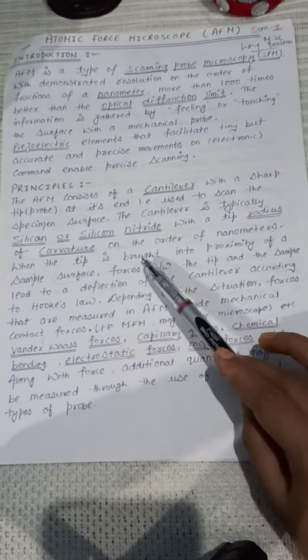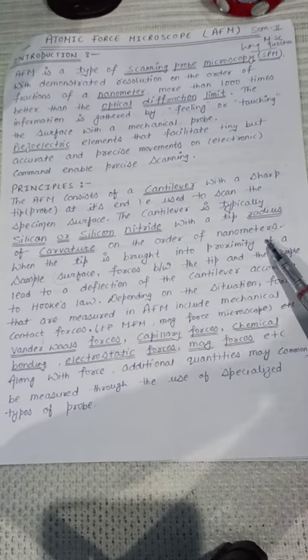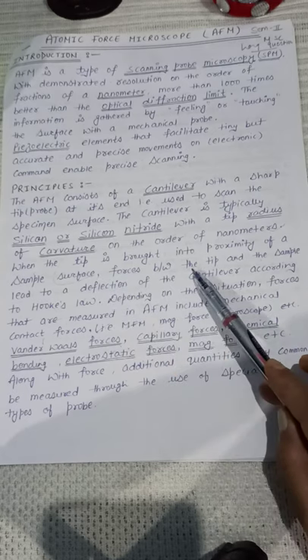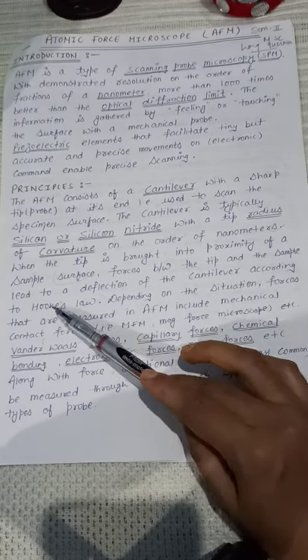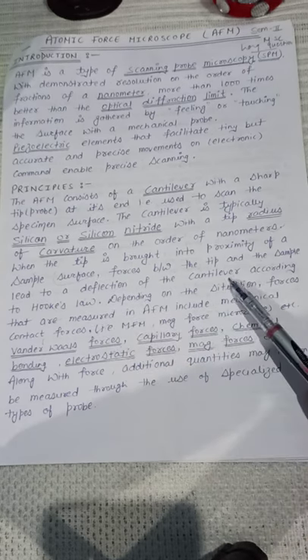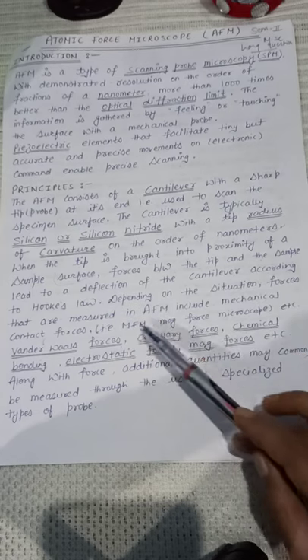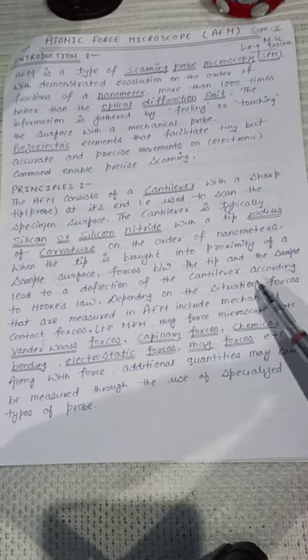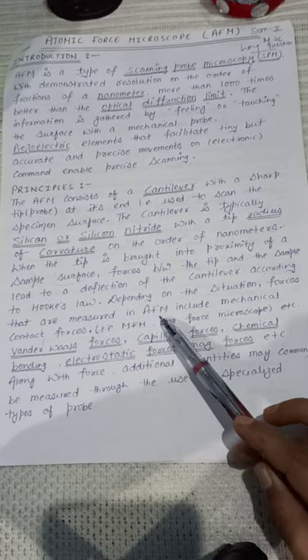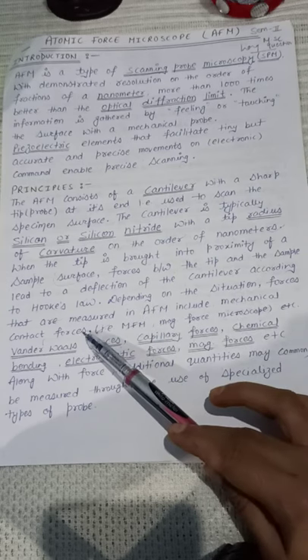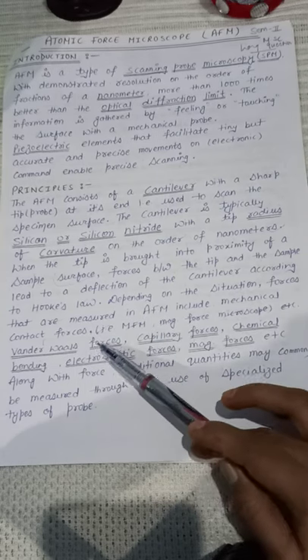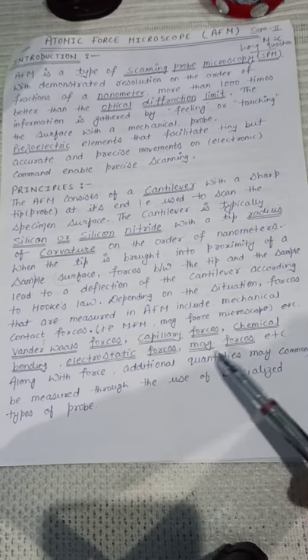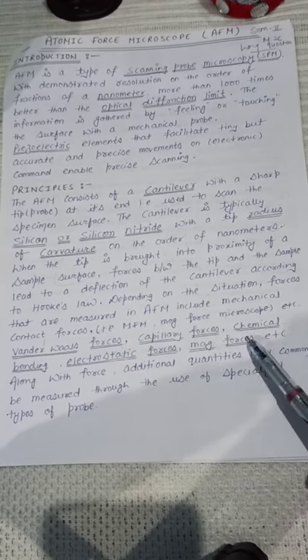When the tip is brought into proximity of a sample surface, forces between the tip and the sample lead to a deflection of the cantilever according to Hooke's law. Depending upon the situation, forces that are measured in AFM include mechanical contact forces (van der Waals forces), capillary forces, chemical bonding, electrostatic forces, magnetic forces, etc.